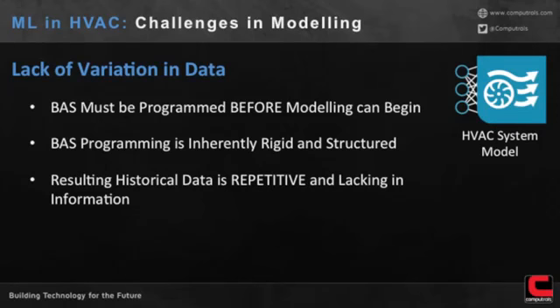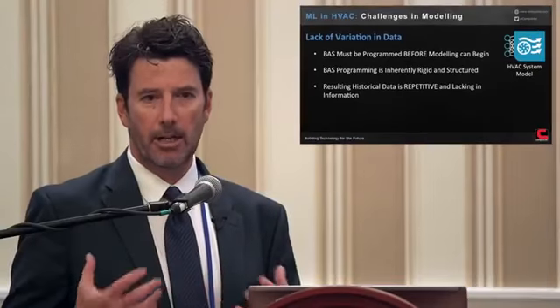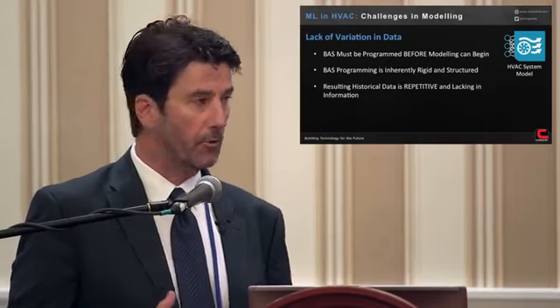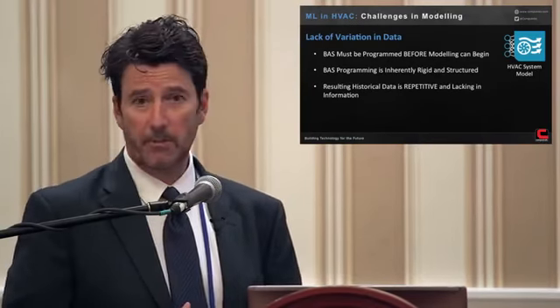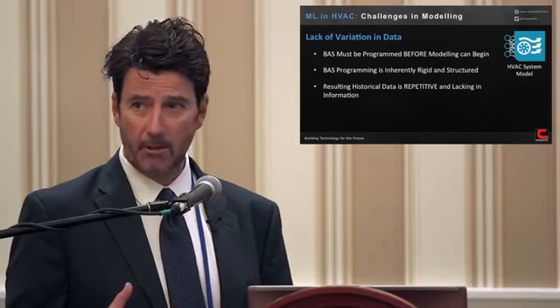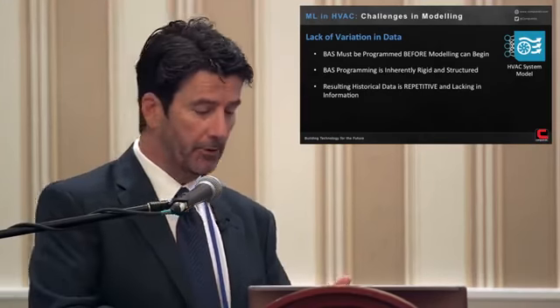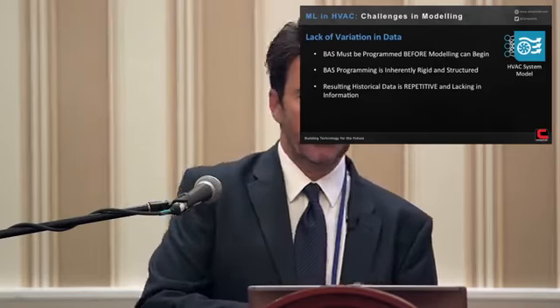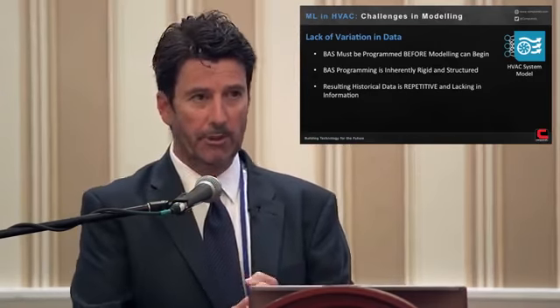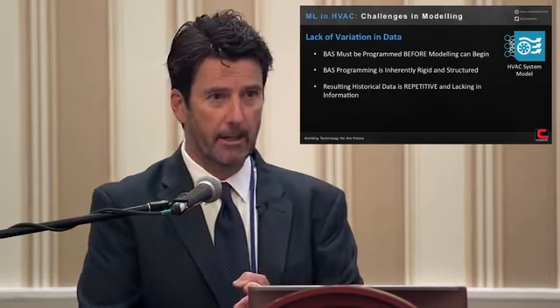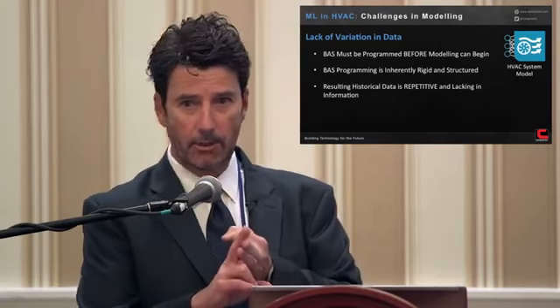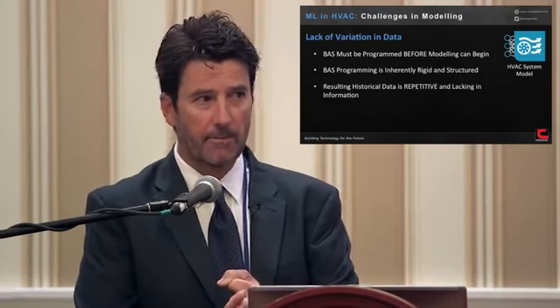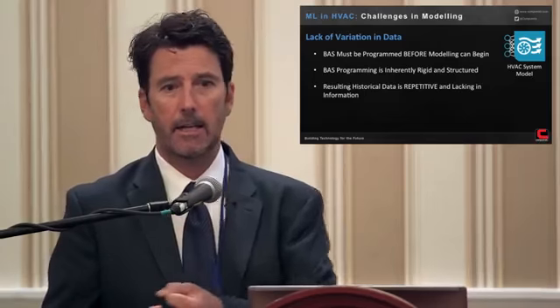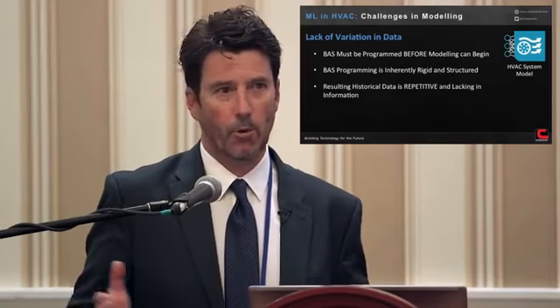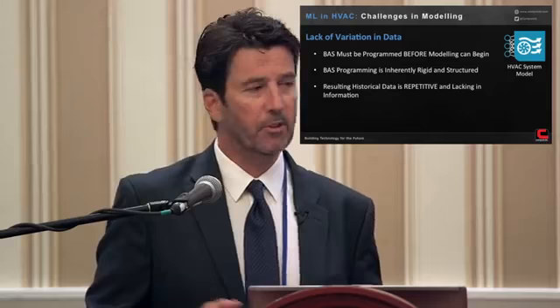What machine learning tries to do, it doesn't just memorize the answer, because that's useless. It tries to make a general thing that can be used in different situations. The problem with building automation is we go in, we have to get the building running, so we put schedules, we put PID loops, we put logic, and it turns out we run the building the exact same way every day. So you look at it for one day, and then you look at it for the next day, it does the same thing. You look at it again and again and again. It doesn't matter whether you have 2 years or 1 year, you're not learning anything.